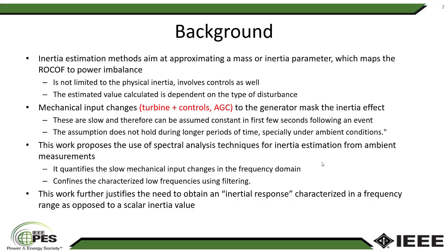But in reality, it's not just limited to the physical inertia of the rotating mass, but it also involves effective controls. You might have noticed that the inertia value that is estimated from events varies a lot. So depending on the nature of the disturbance you study, the inertia estimation value could be totally different.